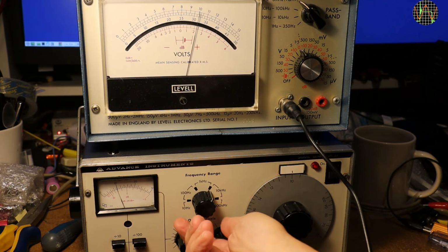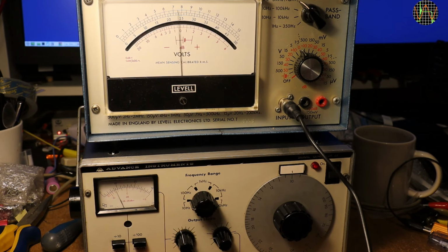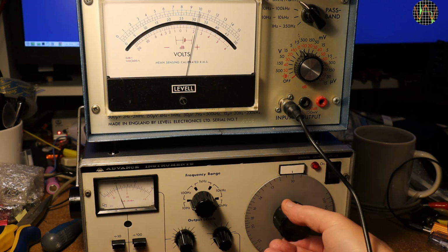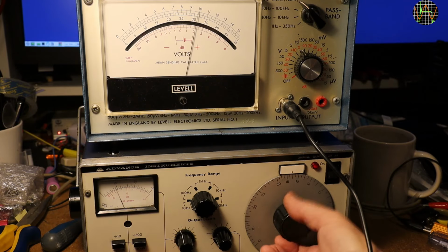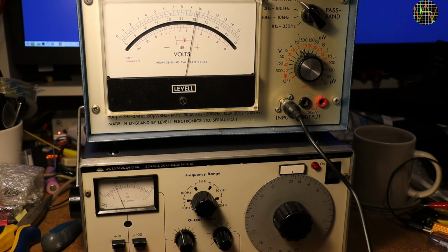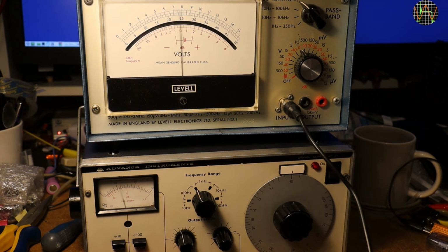The speed of the oscillator amplitude regulation depends on the frequency. As an extreme example, if I switch from 1 volt RMS at 1 kHz to 10 Hz, you see that the amplitude bounces around for a long time before it settles back to 1 volt. I connected the TM3B because its big analog meter makes that easier to see. Even a change from 10 Hz to 20 Hz causes a little upset and several seconds before the amplitude is back to normal. This kind of bounce is really only noticeable in the 10 and 100 Hz ranges, and as you see here in the 100 Hz range it settles already much faster. Just something you have to remember when using these low frequencies.